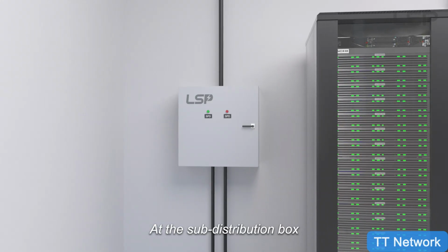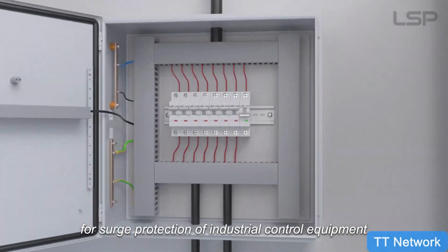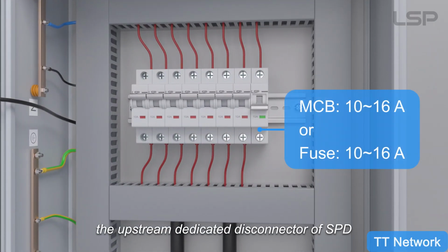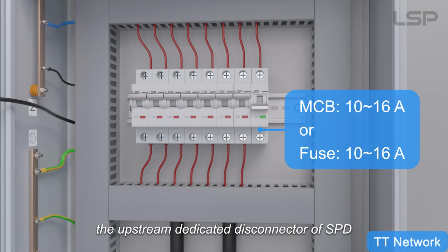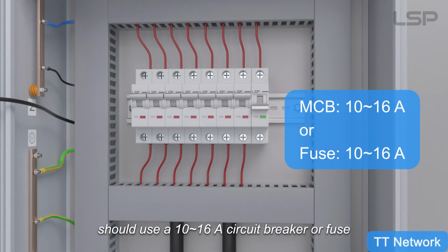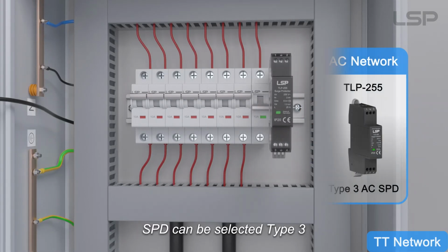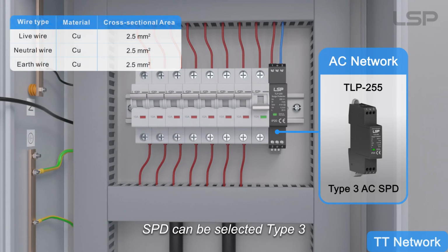At the sub-distribution box, for surge protection of industrial control equipment, the upstream dedicated disconnector of SPD should use a 10 to 16 amp circuit breaker or fuse. SPD can be selected type 3.